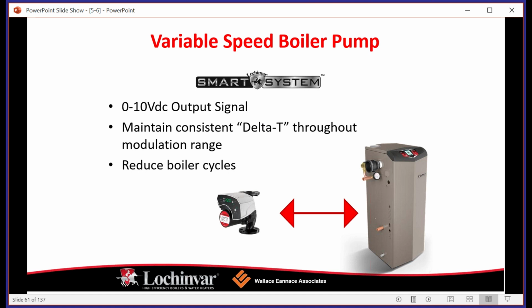One of the other things that the boiler is going to do, a huge component to make it more efficient, is it's going to modulate its fire rate. And that's directly tied into something also called turndown, which I'll explain. So a variable speed boiler pump is very important on modulating boilers. Okay, so what this is going to do, it's going to allow our boiler to tell the boiler pump what speed it should be running at.